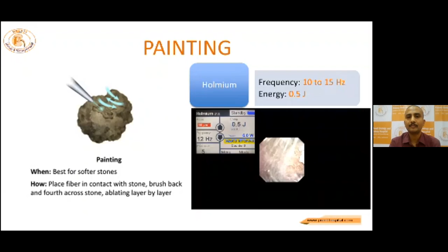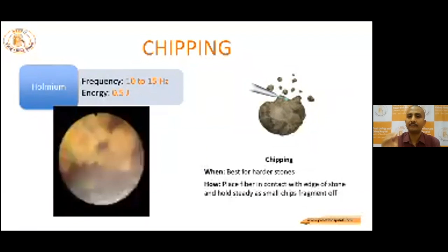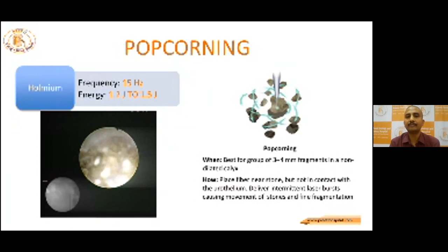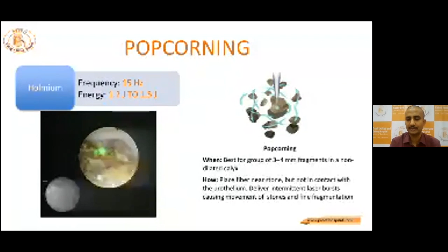The chipping method is nothing but the same painting technique, but we are coming from the edges of the stone. We will be fragmenting it piece by piece as small as possible. We do it most commonly for the hard stones. Here also the energy will be 0.5 joules, that is lowest, and frequency is 10 to 15 hertz. For popcorning, we need very high energy and high frequency. That is, energy is 1.5, which is the maximum energy in a 30 watt machine, and a frequency of 15 hertz, which will make the fragmentation much more efficient.